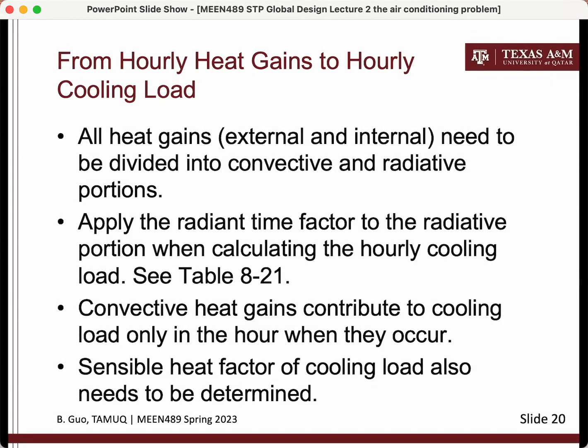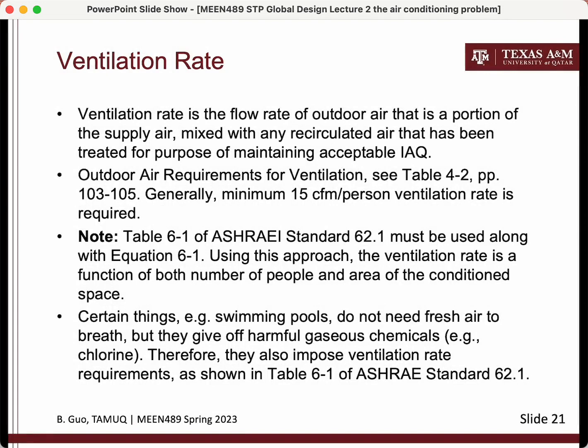In the radiant time series method, after calculating the hourly heat gain we convert the heat gain into hourly cooling load using the radiant time factor. For the air conditioning system, we need to determine the ventilation rate — the fresh air flow rate needed to provide sufficient oxygen to occupants. For a small shelter with a split-body air conditioner where positive control of fresh air is not feasible, the calculation of ventilation rate may not be necessary for air conditioning design purposes, as infiltration is usually relatively high and practically serves the ventilation purpose.